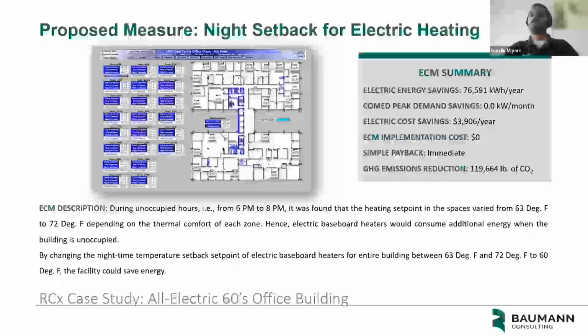By changing the set points, lowering them down to 60 during unoccupied mode, the building will be able to save energy for their electric baseboard heaters. By implementing this measure, the building will be able to save 76,000 kilowatt hours of energy annually. And the implementation cost again for this ECM is zero, because this is something the building engineer can do in-house.